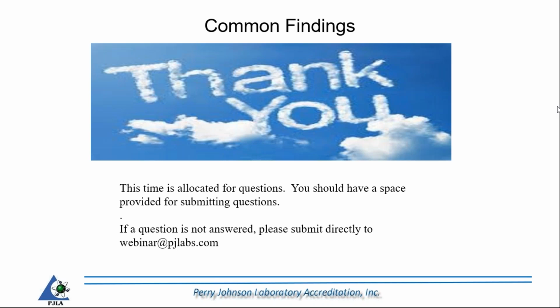This next one, somebody's asking, what if you have an issue with a lab that is accredited and you get two questionable calibrations? Well, the first thing I would do is address that lab itself. If you are accredited, you have a protocol for complaints. That would be your first line. Basically, you have some evidence as to why the results are being questioned. So I would say you always go to the accredited organization first.